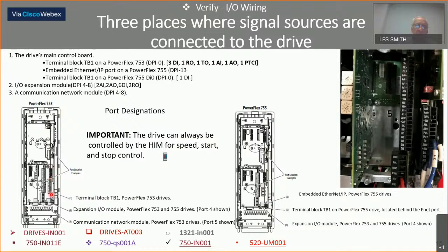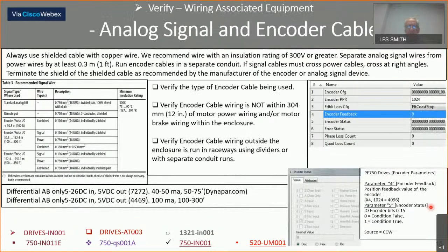This is the motherboard, DPI 0. Same thing over here. You can see on the 755, here's your last octet adjustment for the Ethernet. And over here, since the 753 doesn't have that, we add that over to slot 5. You can see the slot numbers here. As you can in the picture of my demo here, there's slot 5. Digital I/O card is in slot 4. COM card is in slot 6. Just be aware of that.